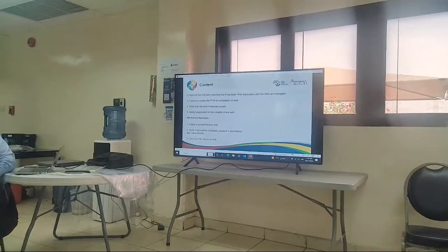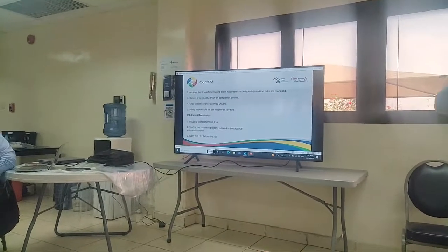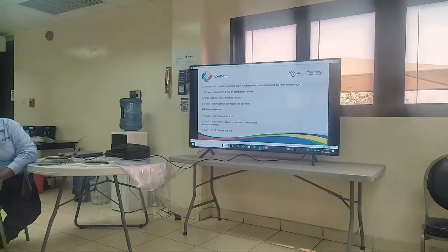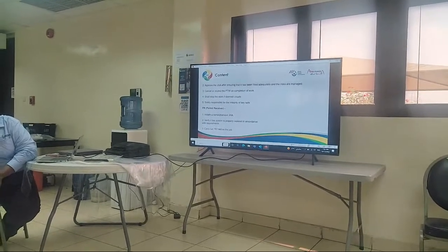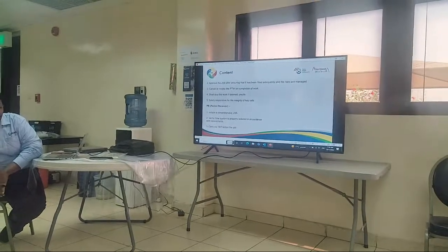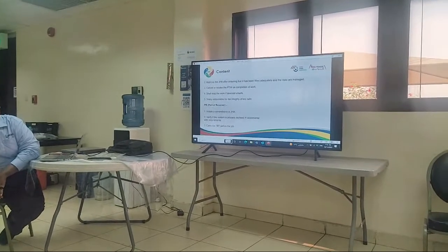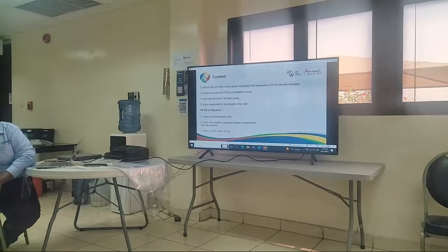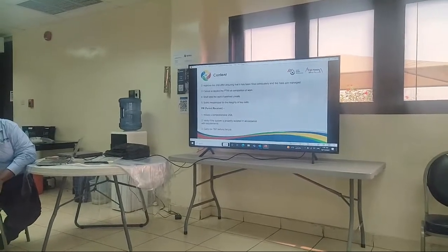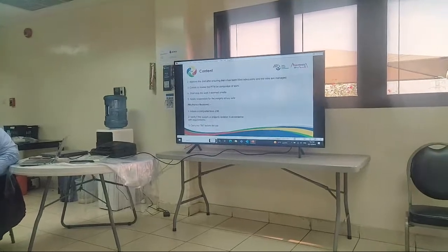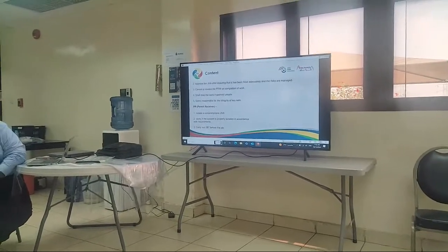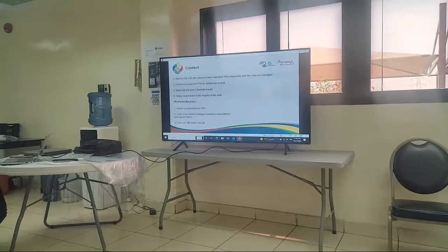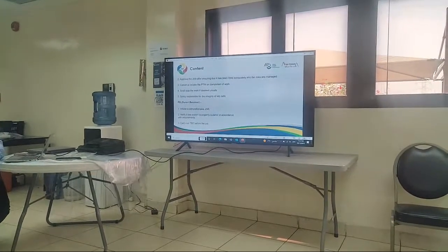Usually, how do you bring the key? Operation, once they isolate, they will give the key. You will go to the CCR. They will give you the key. Yes. Prior to removing the key in the box, you have to ensure that the key from operation side is inside the box. How do we know? How are we satisfied enough to check whether the key from the operation side is there?